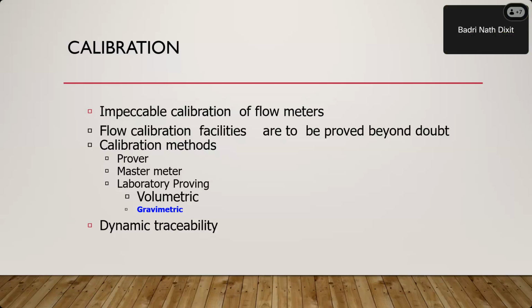Can legal metrology verify and stamp flow meters used for measuring liquids other than liquid petroleum products? Yes. Basically, legal metrology does not restrict itself to a particular commodity or a particular liquid. It is for all types of measurements taking place in transaction or in production. So we can verify and stamp wherever flow meters are used, even if they are not used in any transaction or production. The user can get it verified and stamped if required. Am I right, sir? Yes.